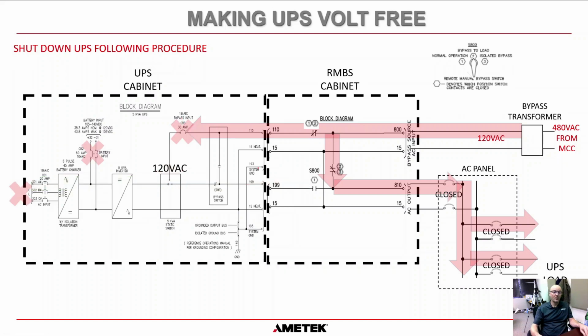And then what we can do is we can go in and shut down the UPS following the procedure on the front of the panel. That will include turning off the AC input to the rectifier and turning off the battery input here. Then, hopefully you have an external disconnect here. You will have to open that, and then go back to this MCC back here and isolate the 480 volts there. Now that will make those two sets of contacts volt free.